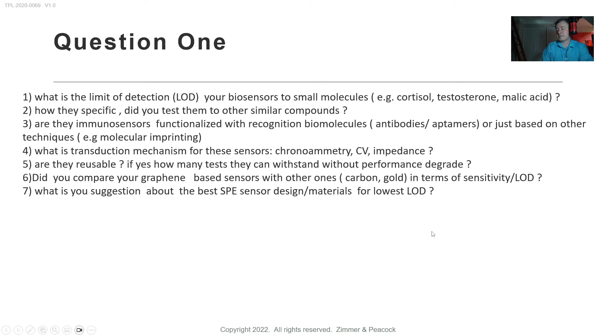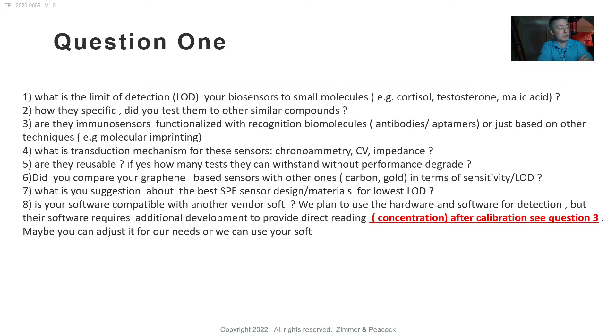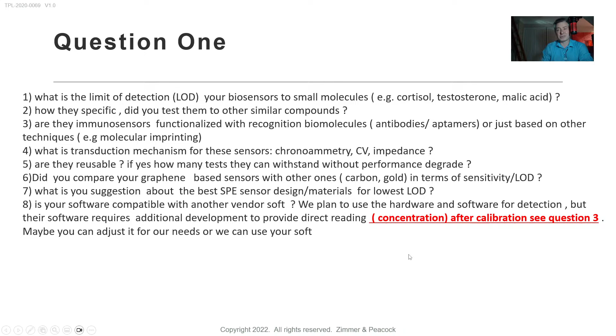So whenever I see this kind of comment about calibration, if you're going to do a point of care or point of need device, you should not ever be doing calibration on that device in the field. It's not going to make for a low cost device, and I would super strongly suggest that. The reason people try to do calibration in the field is because they have irreproducibility on the electrode and therefore the sensor upon the electrode, whereas we don't have irreproducibility. We actually have really good reproducibility. So never do calibration. Calibration should be in the factory, not in the field.